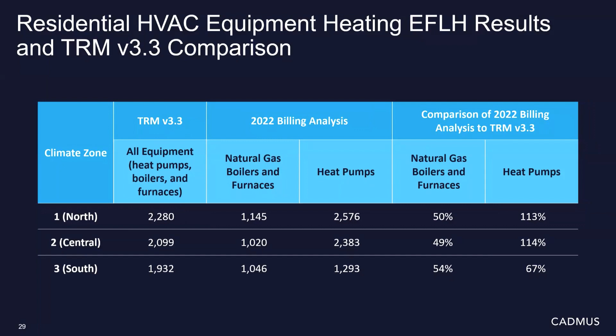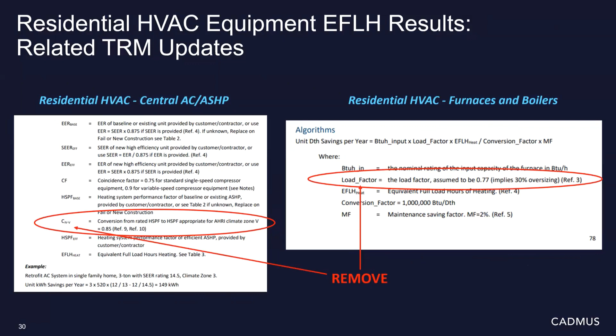So if we incorporate the results of this billing analysis in TRM version 4, we do recommend 2 additional TRM algorithm updates. So for electric heat pumps over on the left, we recommend removing the conversion from the rated heating seasonal performance factor, HSPF, to the climate appropriate HSPF for the algorithm, since this is already reflected in the billing analysis calculation. And then for natural gas-fired boilers and furnaces over on the right, we do recommend taking out that oversizing load factor, since again, this would already be reflected in the billing analysis results. And taking these out of the algorithms has the added benefit of simplifying the algorithms for our customers.